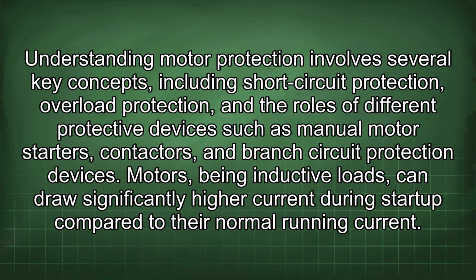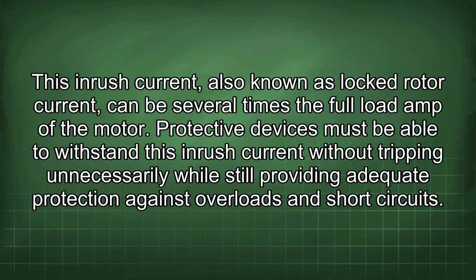Understanding motor protection involves several key concepts, including short circuit protection, overload protection, and the roles of different protective devices such as manual motor starters, contactors, and branch circuit protection devices. Motors, being inductive loads, can draw significantly higher current during startup compared to their normal running current. This inrush current, also known as locked rotor current, can be several times the full load amp of the motor.